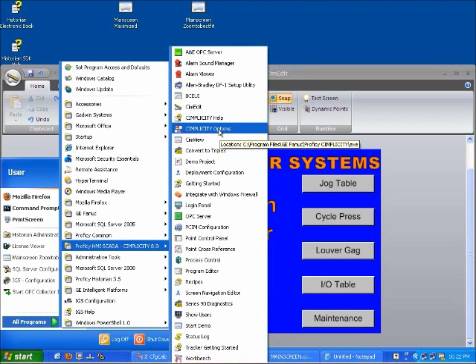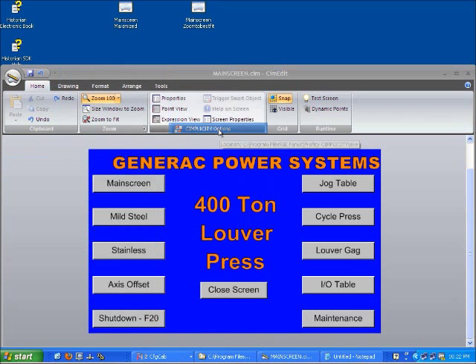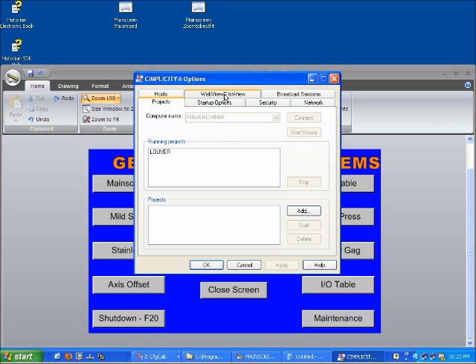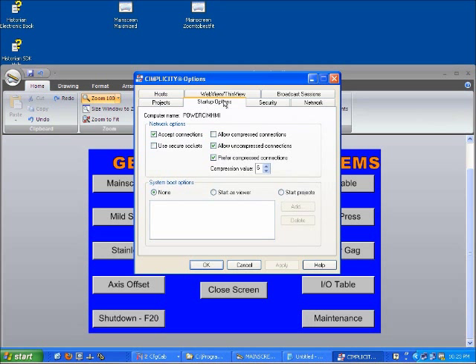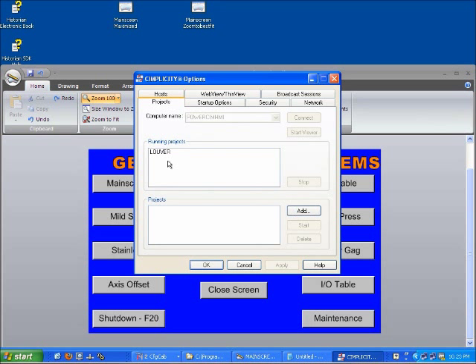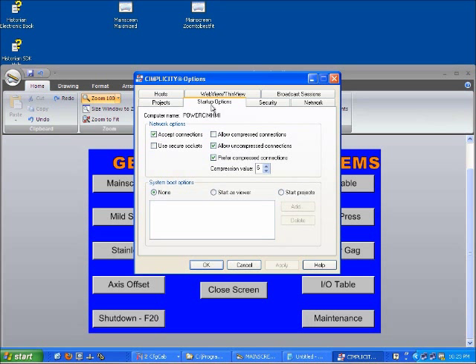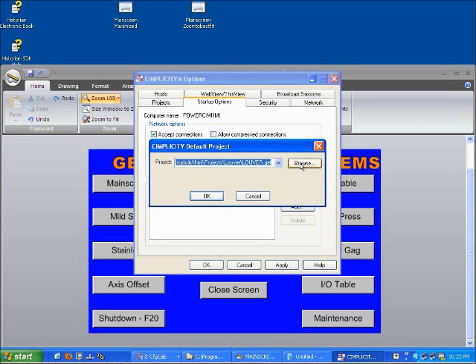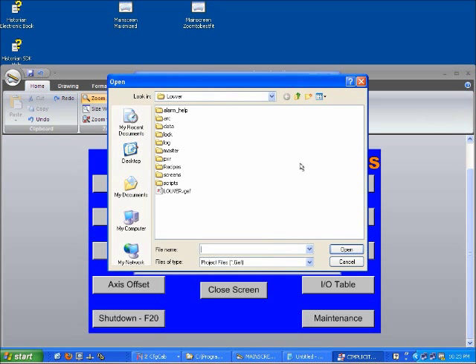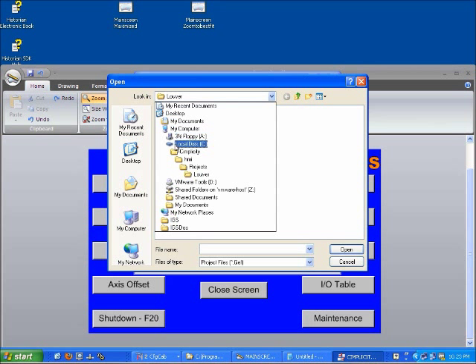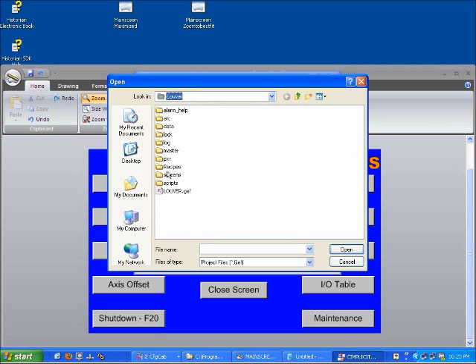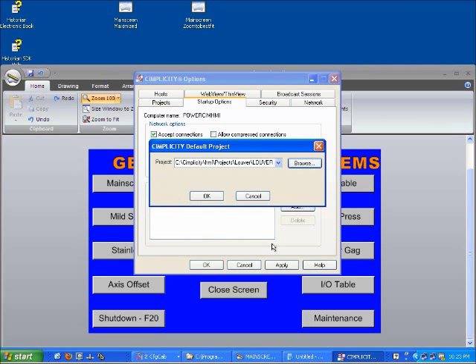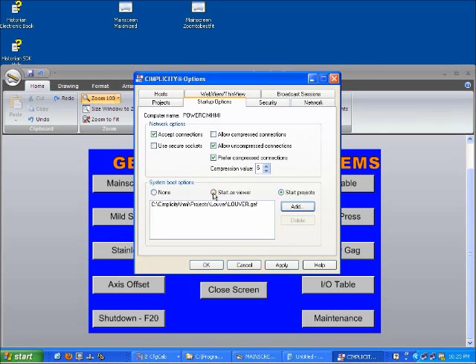Programs, CIMPLICITY SCADA, CIMPLICITY Options. All right, we'll fire that up here. If we look at the startup options, right now we can see that the Louver project is running. We see that here, running projects. Now in startup options, we could add that project to start up when the computer starts. I'll navigate to wherever I parked that guy. We see I parked him at C Simplicity HMI Projects Louver. And there he is right there, say OK, and now he's here when we start up. I would say apply and OK and all that stuff.